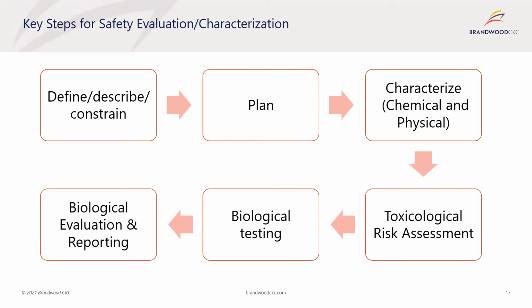An important thing to do is to start working on biocompatibility at the beginning of the project. It isn't something that you can just slap on the device at the end of the project. Even though biological or safety evaluation is a validation activity and has to be done on the final finished products, you should start at the beginning really thinking about this. The toxicological risk assessment and biological testing is used to estimate risk. Those risks then need to be evaluated. Are they acceptable or not acceptable? And here's where a multifaceted, multidisciplined team really comes into play.